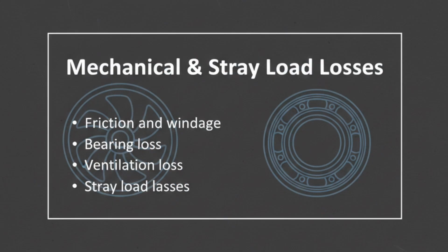In addition to electrical losses, we have mechanical losses such as bearing friction, air friction or windage, and losses in cooling fans. These losses depend mainly on speed and construction rather than load. There are also stray load losses, which are small but unavoidable losses caused by leakage flux, harmonics in current and flux, and non-uniform distribution of current in conductors. Modern standards include stray losses when calculating efficiency.